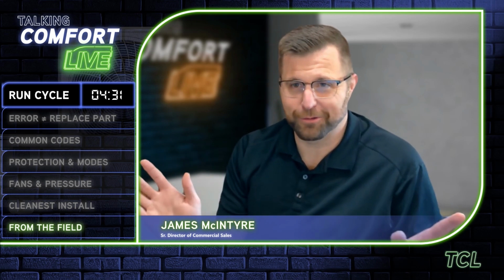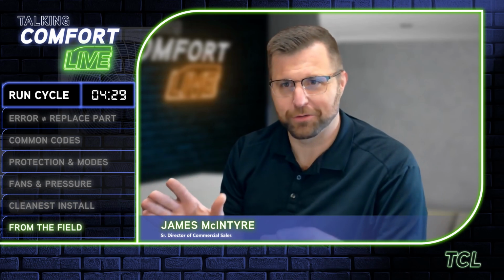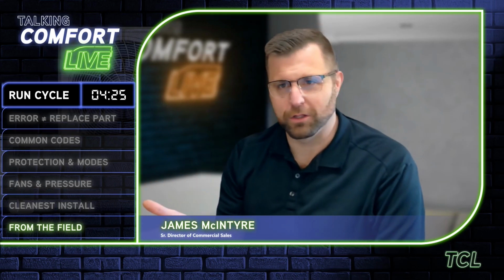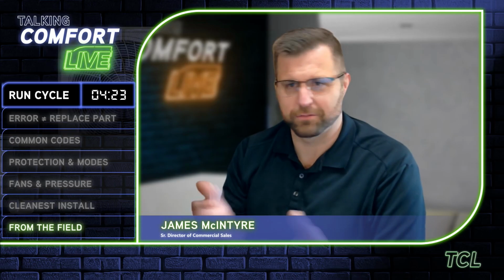Okay, so I'm going to go out on a limb here and say that there was no heat load calculation done on that. I understand that's what the spec says and all that stuff, but there's no heat load or heat loss calculation done on that. That's precisely what the reason is.